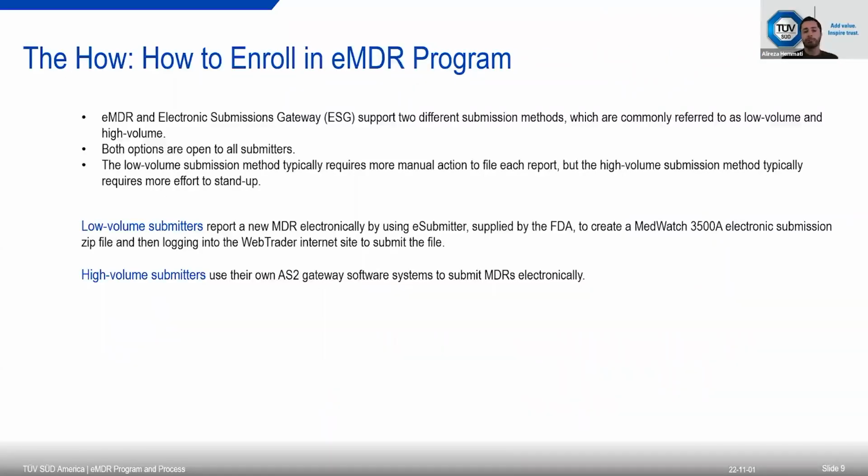So how to enroll in eMDR, the electronic MDR program. The final rule that, as I mentioned, came into effect in 2015 did not change what must be included in an MDR report or when the report should be submitted. The primary change is the method of submitting MDRs to FDA, which has changed for manufacturers and importers from paper to electronic method.